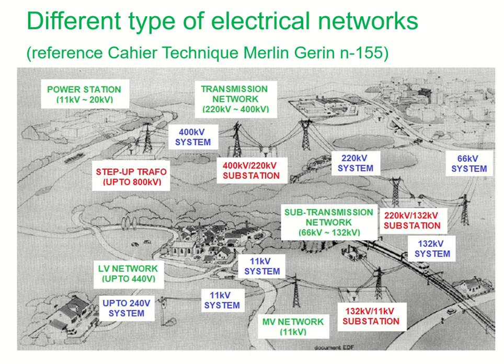Mostly power is generated at 11 kV and 20 kV, but we cannot transmit power at this level because due to the long lengths of transmission lines the losses would be very high — the lower the voltage, the higher the current, and large cross-section cables would also be required to reduce power losses. So in practice, a grid station or substation is located near the power house where the power is stepped up using a step-up transformer.